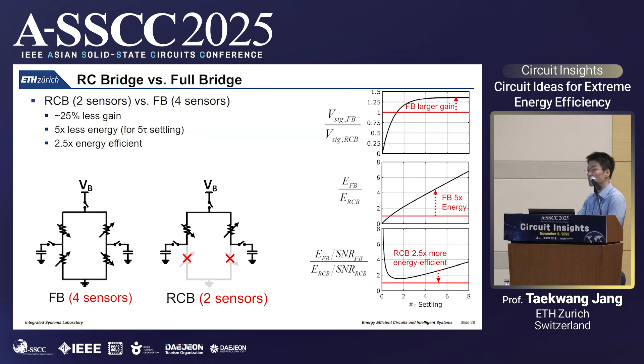If you are comparing with the full bridge, of course, with the full bridge you can use 4 sensors if you are using a Wheatstone bridge, but the RC bridge is limited to only 2 resistors. So even though we have the penalty of using only 2 resistors, which is also good from the integration perspective because you only need to include 2 sensors instead of 4, still comparing to the full bridge using 4 sensors, the RC bridge is about 2.5 times more energy efficient. So I believe the RC bridge is actually a better way if you're looking into resistance to voltage conversion applications.